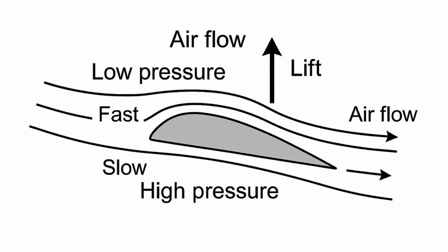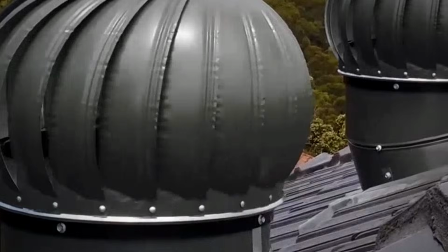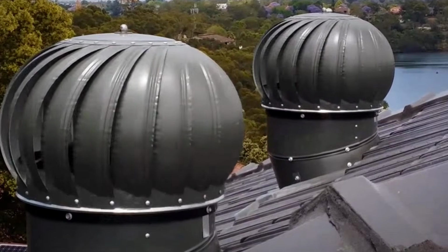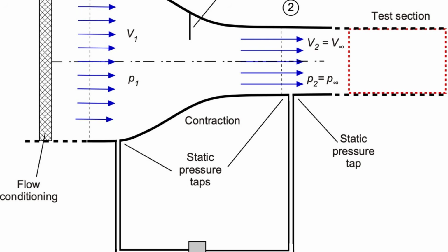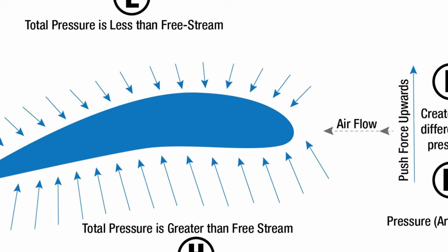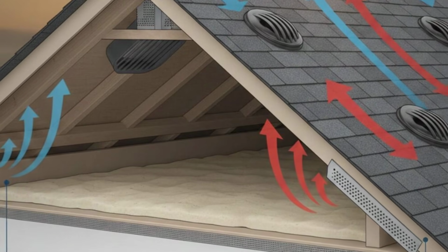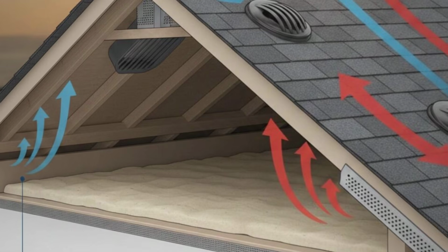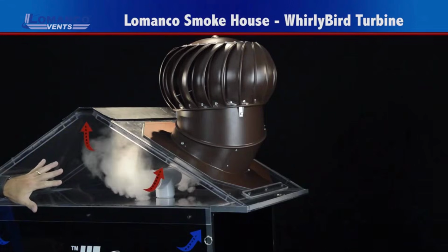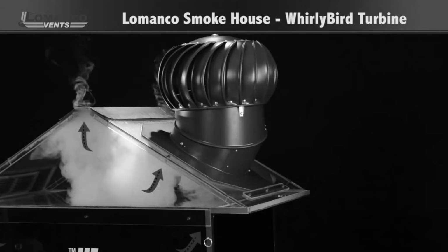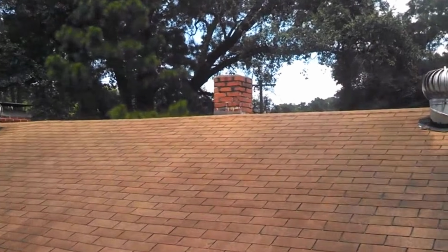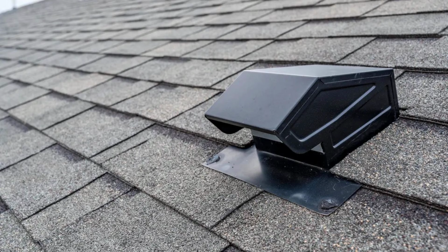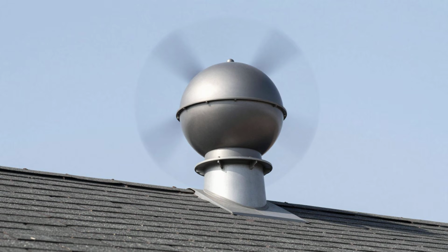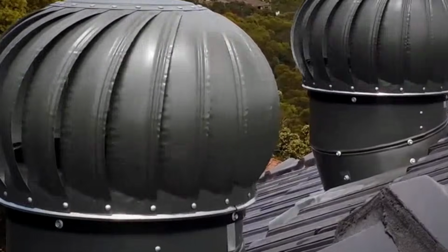The first is Bernoulli's principle. As wind passes across the curved vanes of the turbine head, the air is forced to accelerate. When air speeds up, its pressure drops. This creates a zone of low pressure inside the turbine that generates a suction effect, actively pulling warm air upward from the attic and expelling it outside. The critical distinction here is that unlike a static vent that simply sits there and waits for air to drift out on its own, the turbine ventilator uses the kinetic energy of passing wind to physically drag air out of the building. The stronger the wind, the harder the turbine pulls.